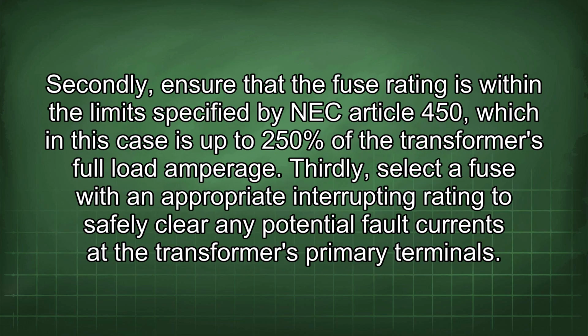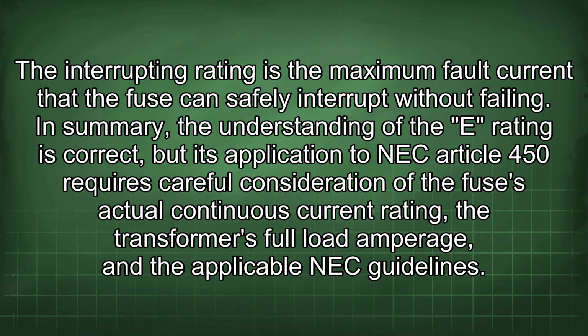Secondly, ensure that the fuse rating is within the limit specified by NEC Article 450, which in this case is up to 250% of the transformer's full load amperage. Thirdly, select a fuse with an appropriate interrupting rating to safely clear any potential fault currents at the transformer's primary terminals. The interrupting rating is the maximum fault current that the fuse can safely interrupt without failing.